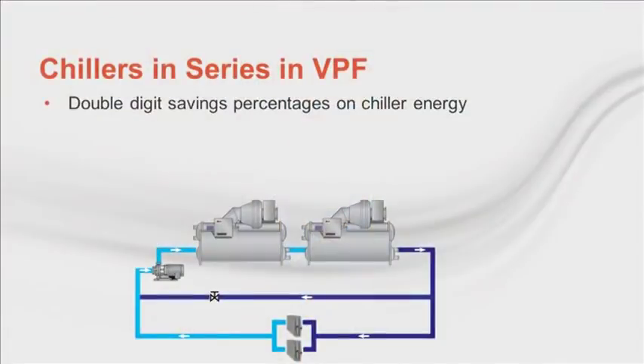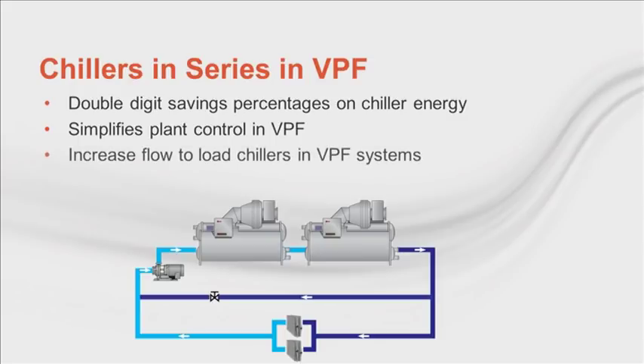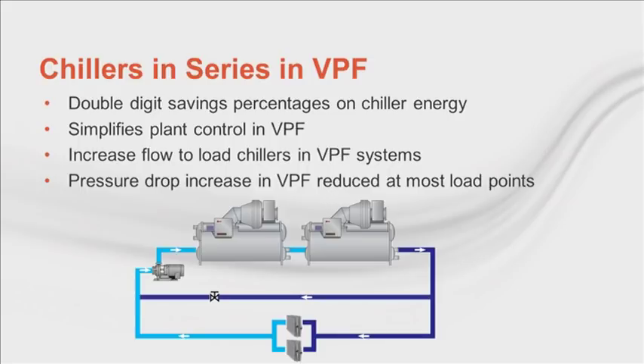Should we pipe the chillers in parallel or in series? In a variable primary flow system, we're balancing a potential increase in pump energy with a reduction in chiller energy. Double-digit chiller energy savings are quite possible. A huge advantage of a series system in a variable primary configuration is control simplicity. The transition from 1 to 2 chillers and back can be seamless. We increase chiller flow to load our chillers. What we really want to know is how much of the time my series configuration will increase pump energy once the flow rate is variable.